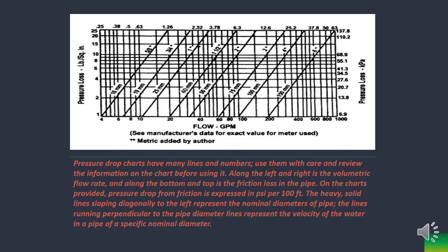The pressure drop chart in the figure applies to pressure drops as water flows through a water meter. Water meter design typically reduces pressure significantly. It should not be neglected in pressure drop computations.